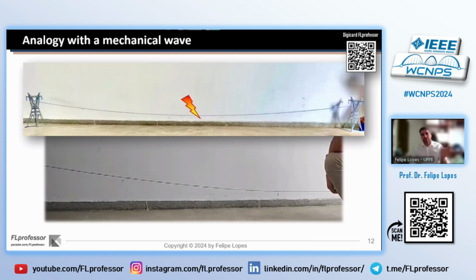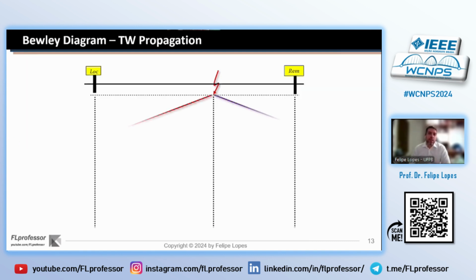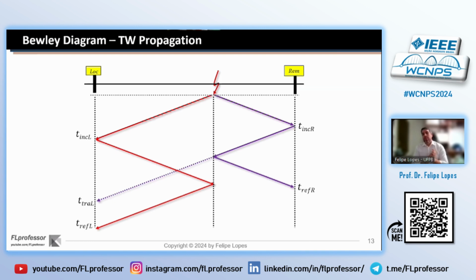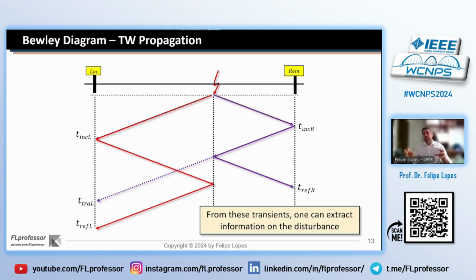And since they propagate and reflect from the system discontinuities, we can draw the Bewley diagram, which represents the traveling wave propagation. And these waves propagate from the fault toward the line terminals, where they find discontinuities because there are other equipment connected at both terminals. Then they reflect back to the fault point. At the fault point, if we are talking about a permanent fault, they will reflect again, and part of these waves will be transmitted, passing through the fault toward the opposite terminal. But the main information here is that from the transients that these traveling waves will create, we can extract information on the disturbance. And this is the main principle of traveling wave protection functions.